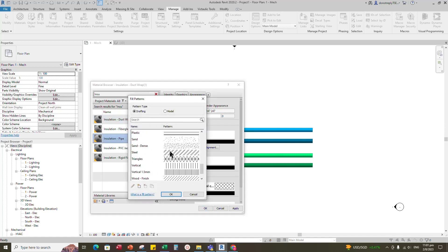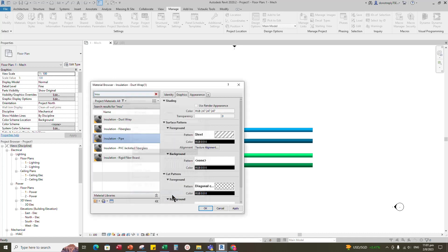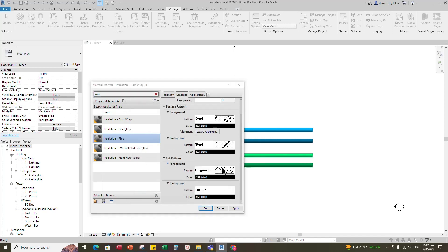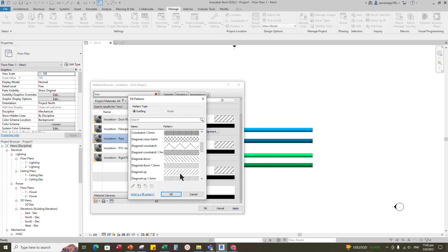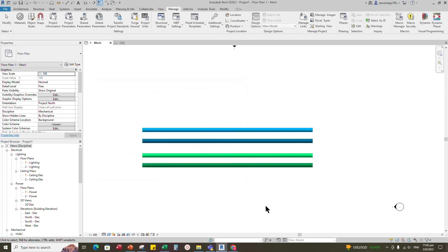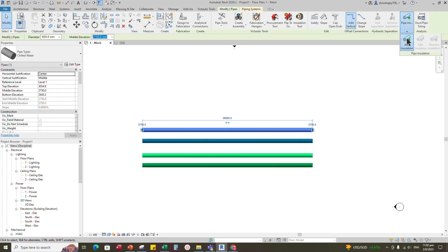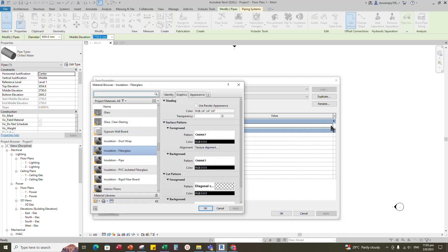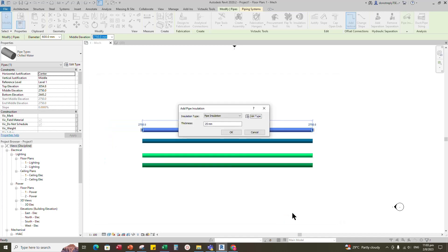Add a pattern for the surface pattern — select the steel pattern for pipe insulation. Add the pattern for both surface and cut pattern. Click Apply and OK. Select the chilled water supply pipe and add insulation. Duplicate the existing insulation type and rename it to Pipe Insulation. Add material for pipe insulation, select the Insulation Pipe material, and click OK. Set 50mm for thickness and click OK.